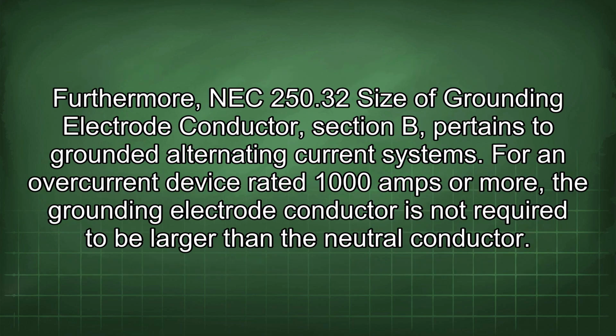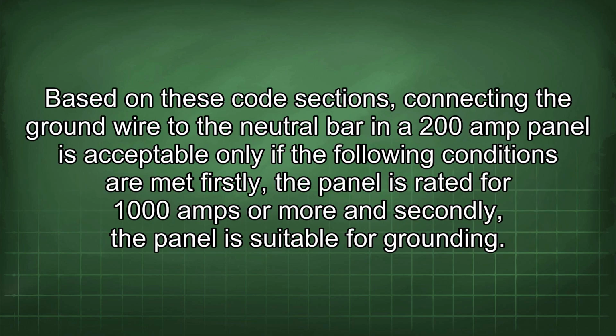Furthermore, NEC 250.32 size of grounding electrode conductor, Section B, pertains to grounded alternating current systems. For an overcurrent device rated 1000 amps or more, the grounding electrode conductor is not required to be larger than the neutral conductor.